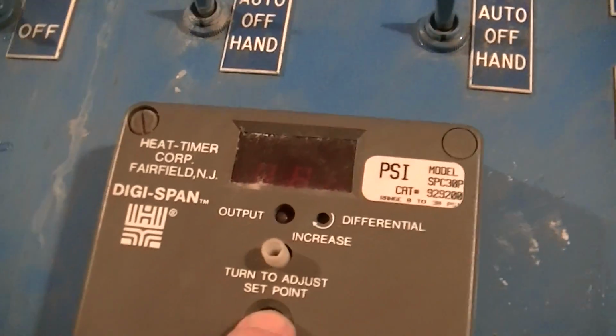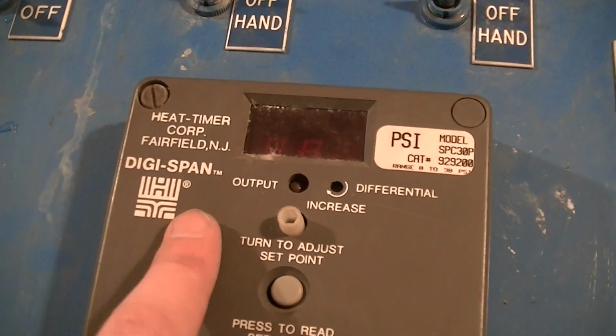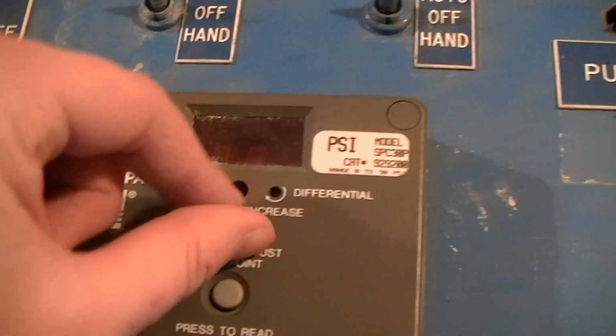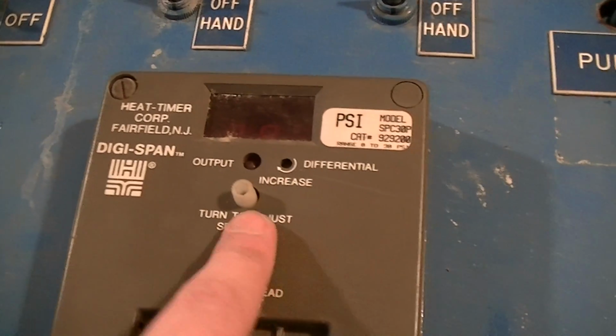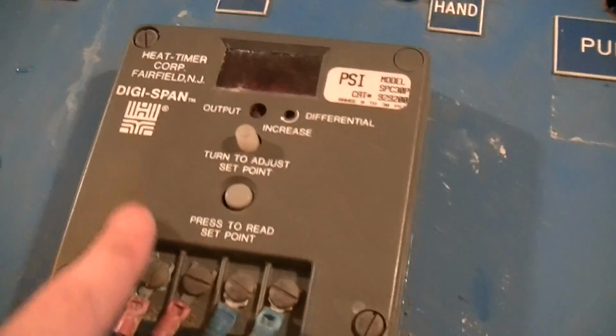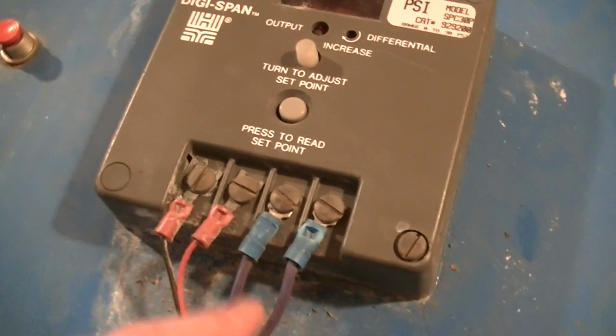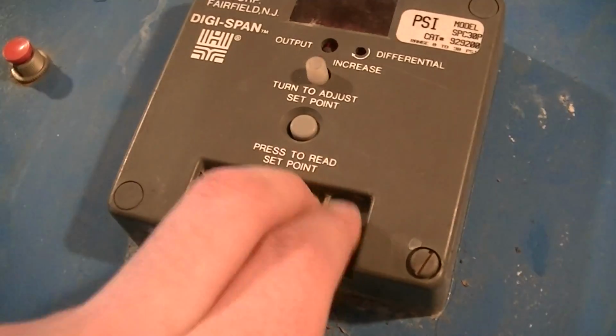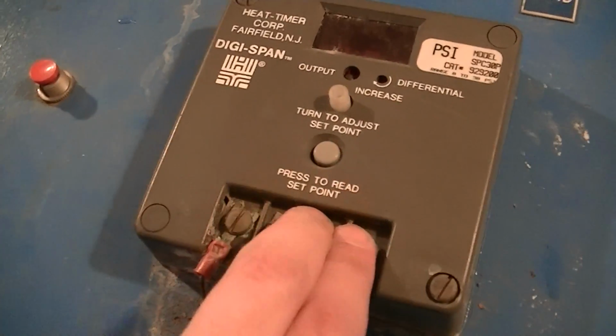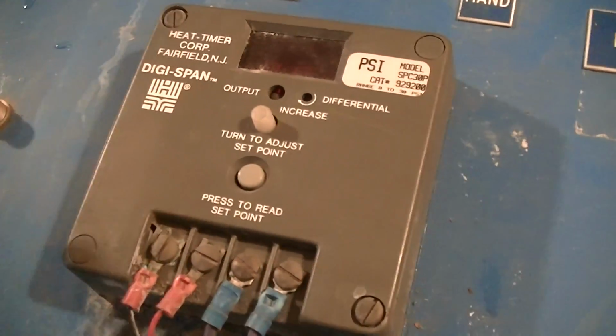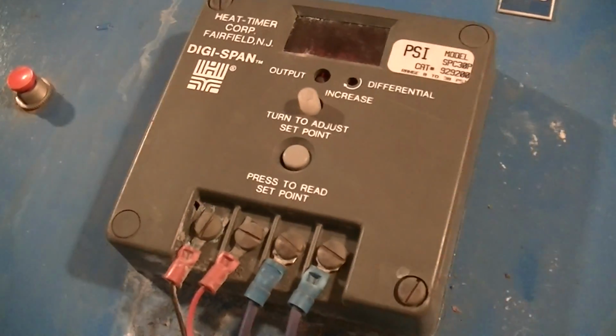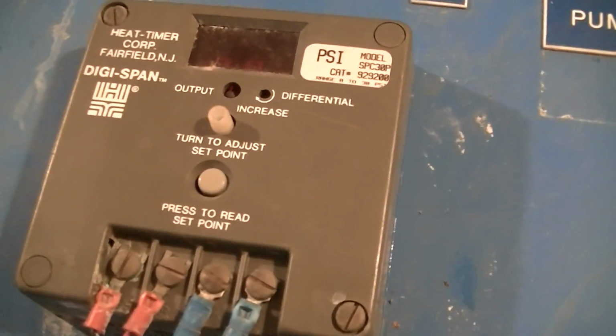Also got this little Heat Timer Corporation Digispan. It's basically a transducer operated relay. It runs on 24 volts AC. That's why the purple wires are for it, of course. So that wouldn't be an electrocution hazard under most things, but then again, in an industrial type application, you're not going to be randomly sticking your fingers on terminals, at least not if you want to live long.